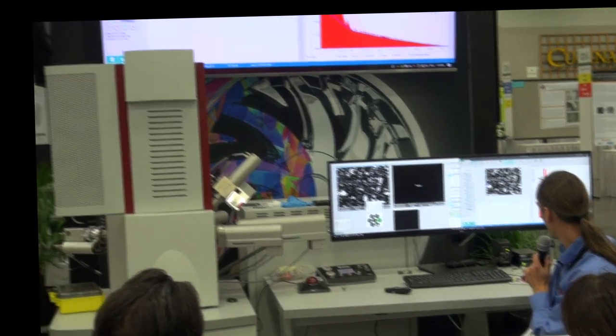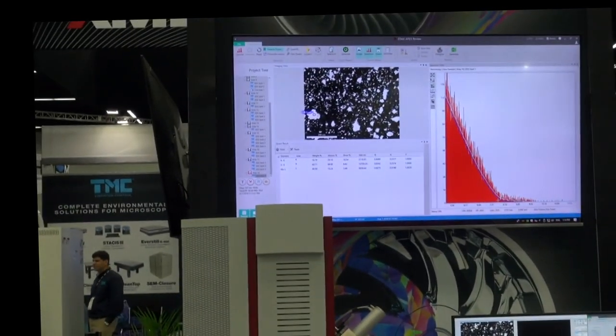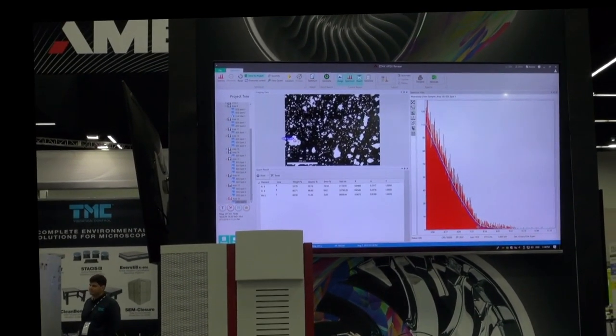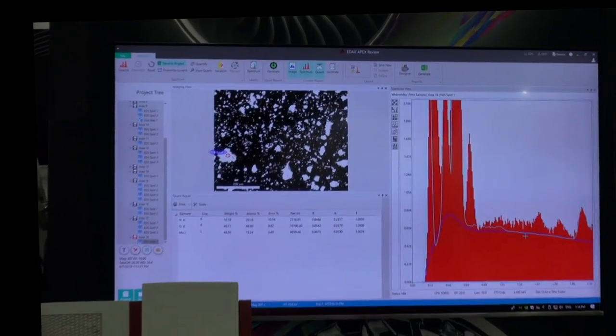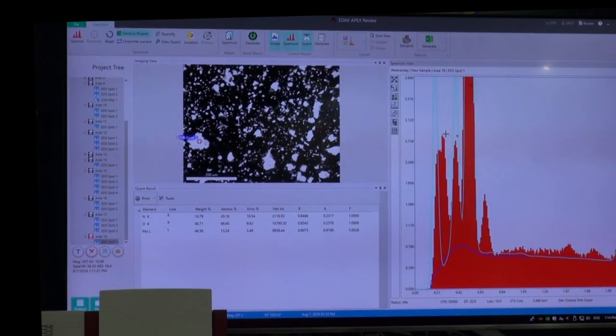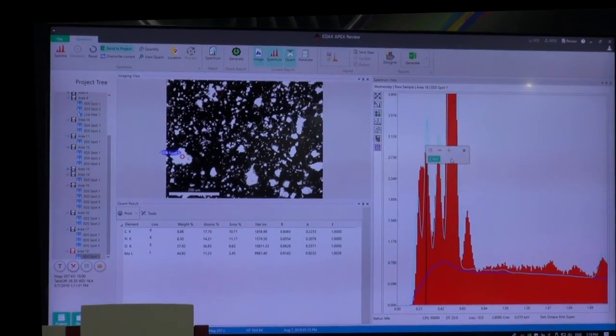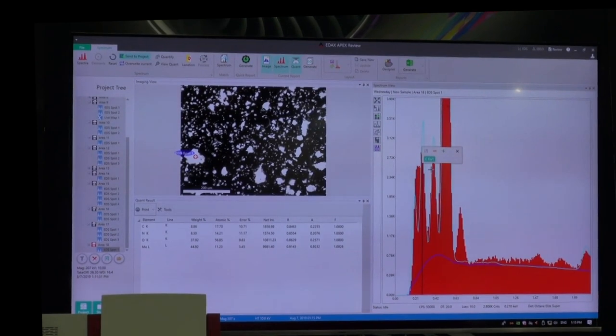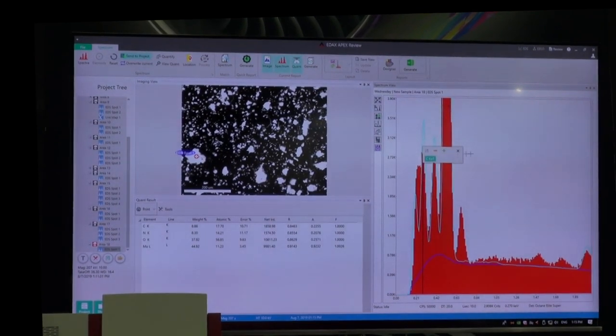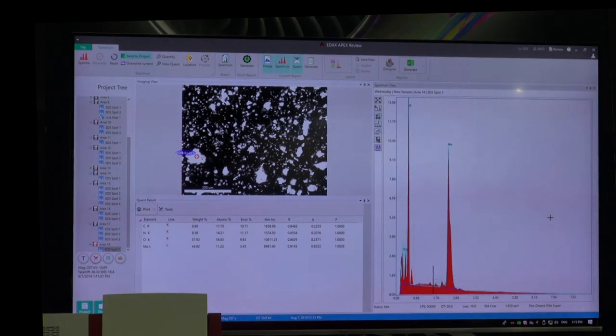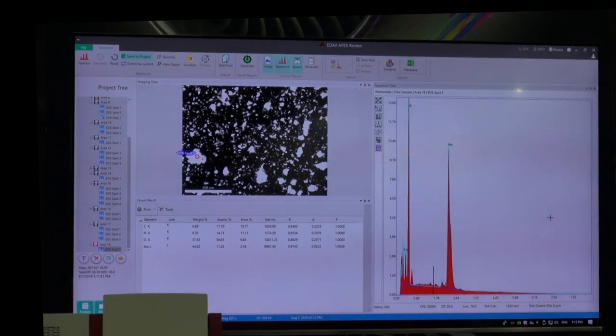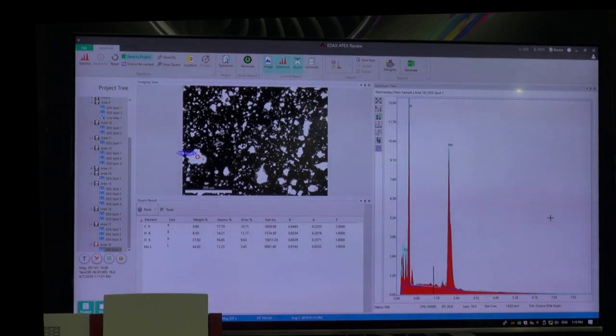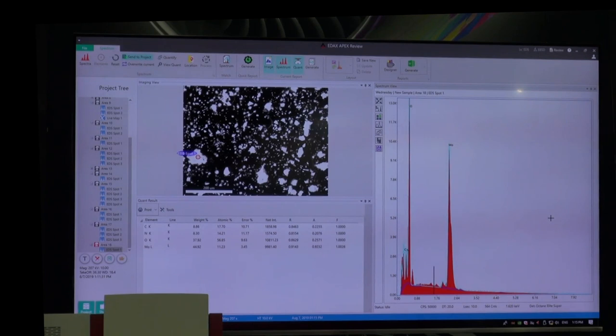The SNP does perform well and meets some requirements. If I'm looking just for qualitative analysis on irregular samples or particulates, I don't necessarily want to see the big misfit from a Bremsstrahlung model knowing I can't do quant on it. But it does make it easier and gives prettier curves when you're just doing qualitative analysis. Now I've switched into the SNP model — the model drops down nicely to where the background drops off, with a reasonable fit all the way down. You don't see any absorption lines and not much change when including or excluding peaks, because it's just a math filter.